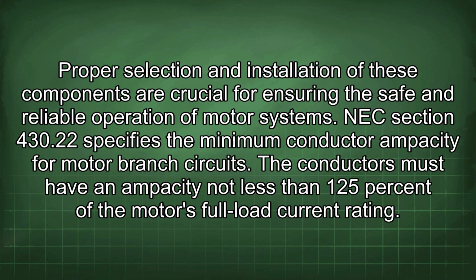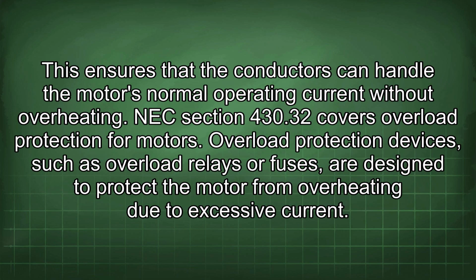Proper selection and installation of these components are crucial for ensuring the safe and reliable operation of motor systems. NEC Section 430.22 specifies the minimum conductor ampacity for motor branch circuits. The conductors must have an ampacity not less than 125% of the motor's full load current rating. This ensures that the conductors can handle the motor's normal operating current without overheating.